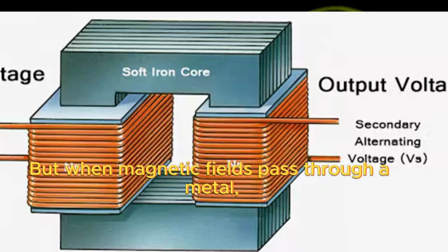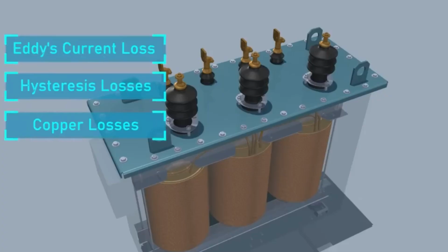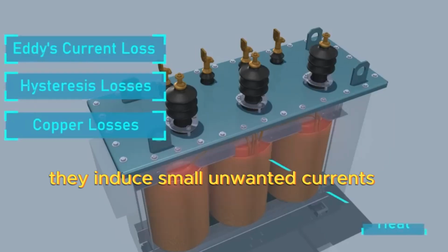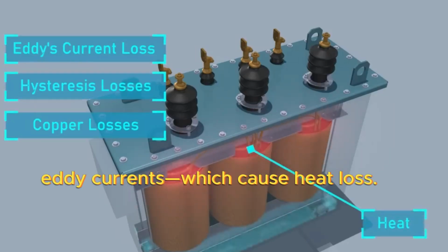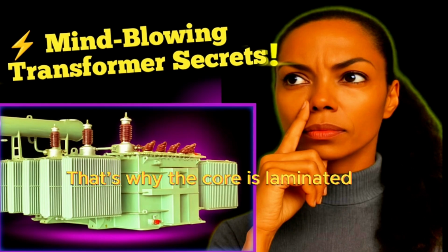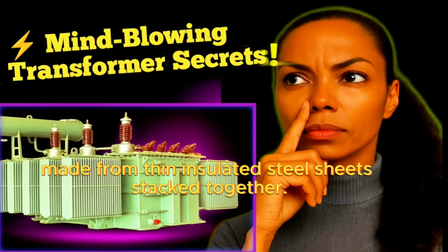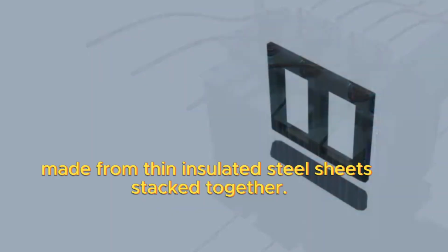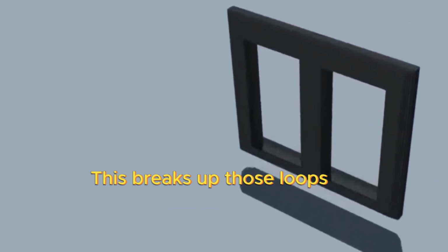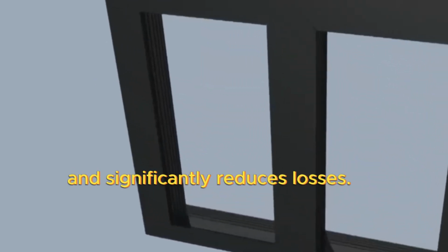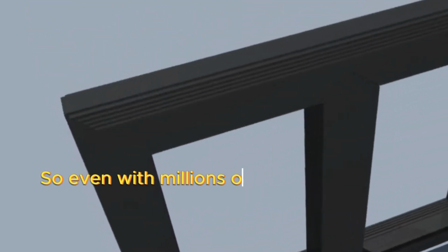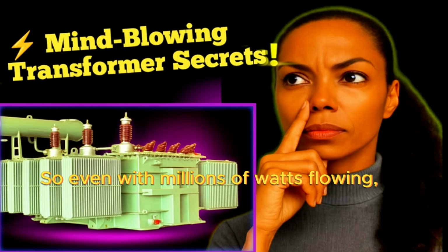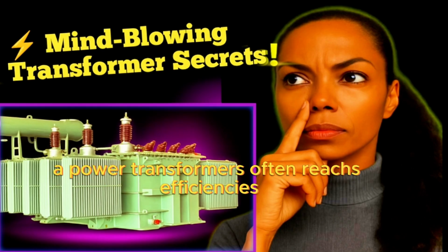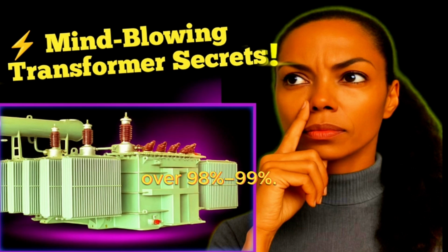But when a magnetic field passes through a metal, it induces small unwanted currents, eddy currents, which cause heat loss. That is why the core is laminated, made from thin insulated steel sheets stacked together. This breaks up the loops and significantly reduces loss. So even with millions of watts flowing, a power transformer often reaches an efficiency of over 98% to 99%.